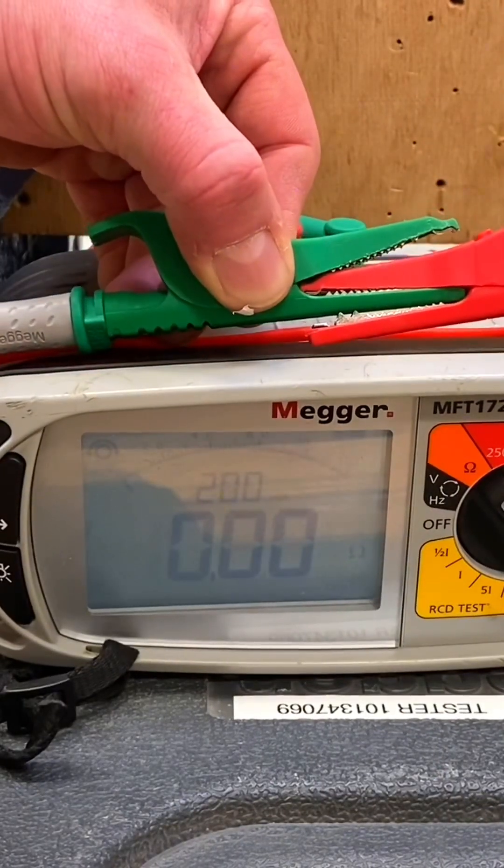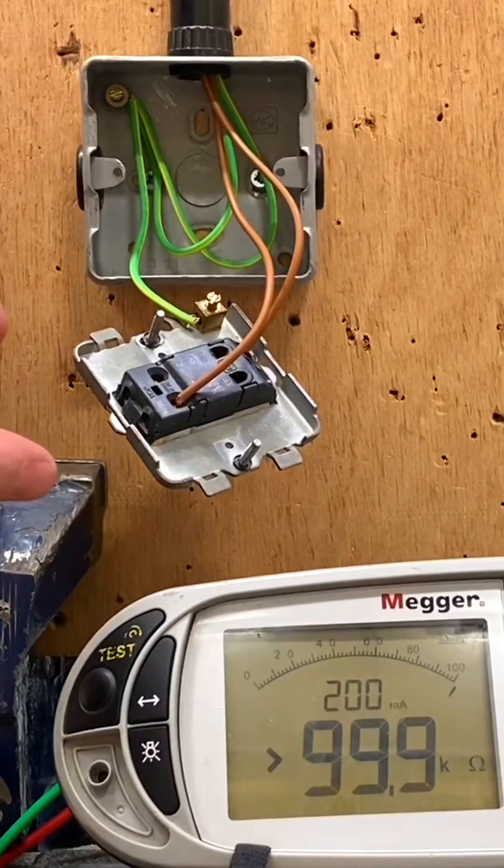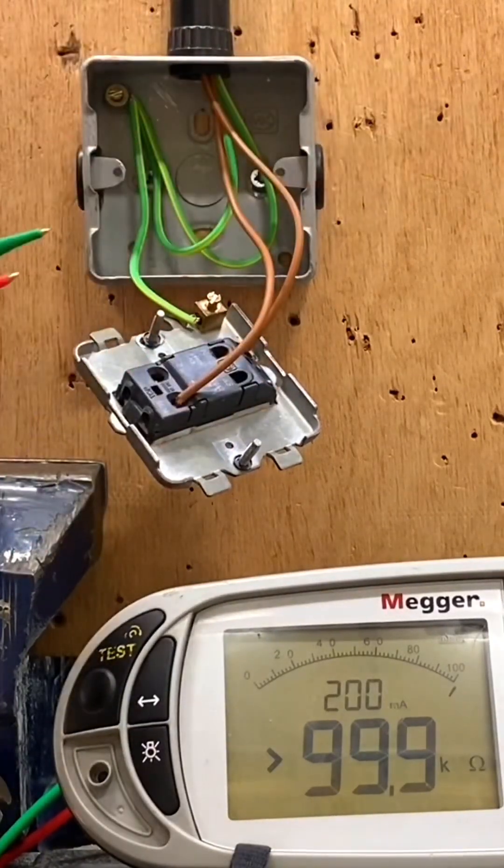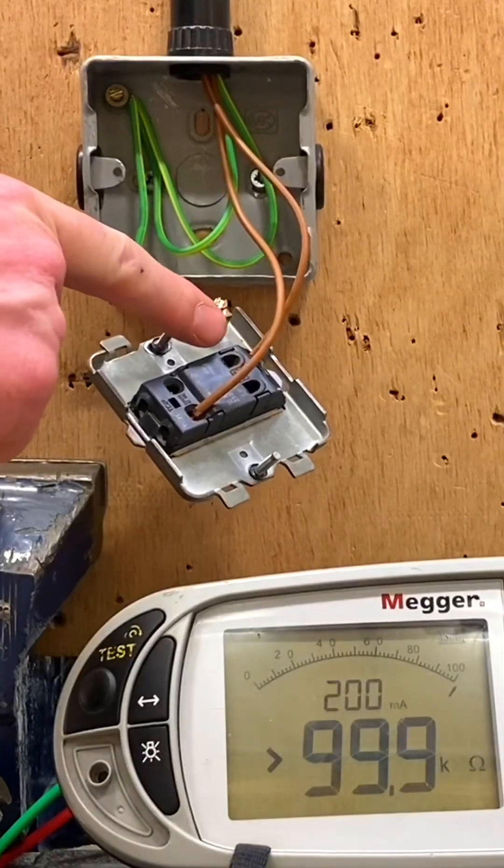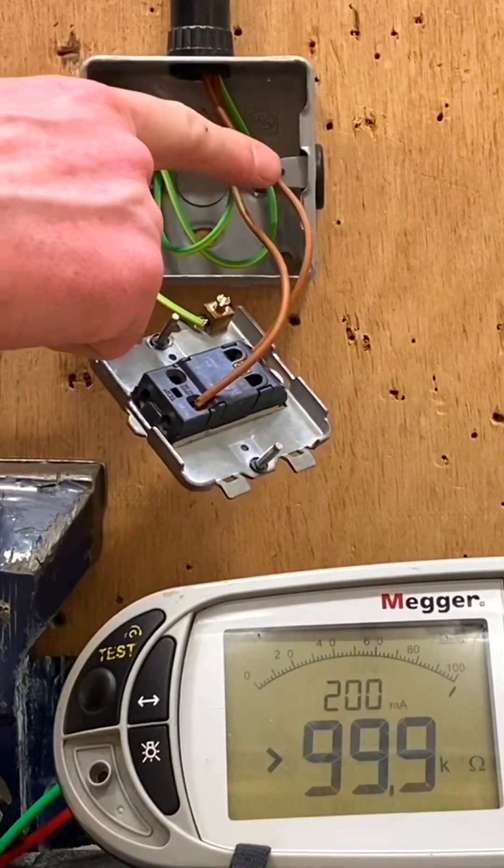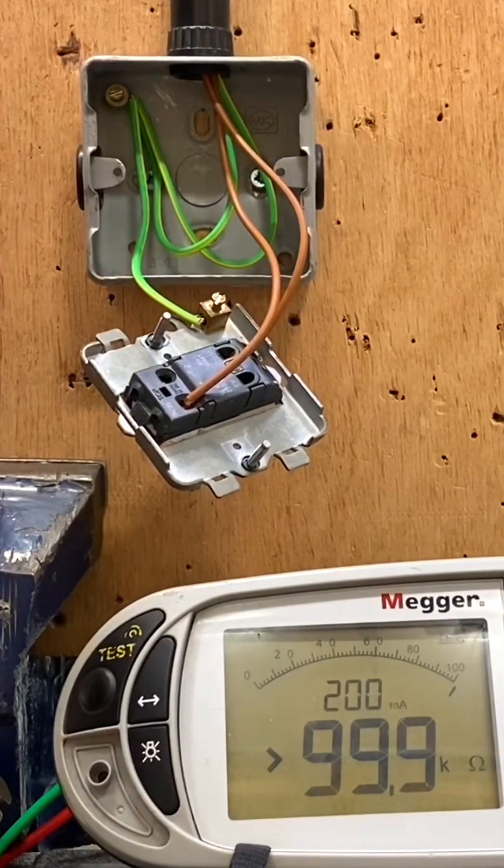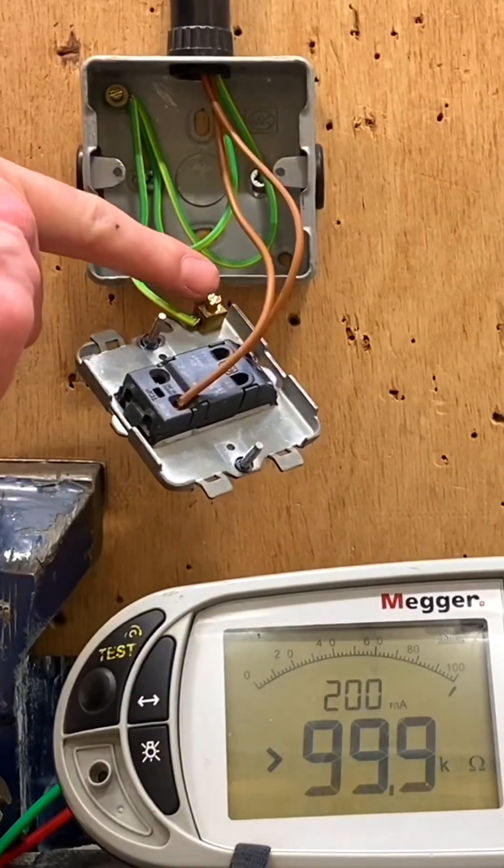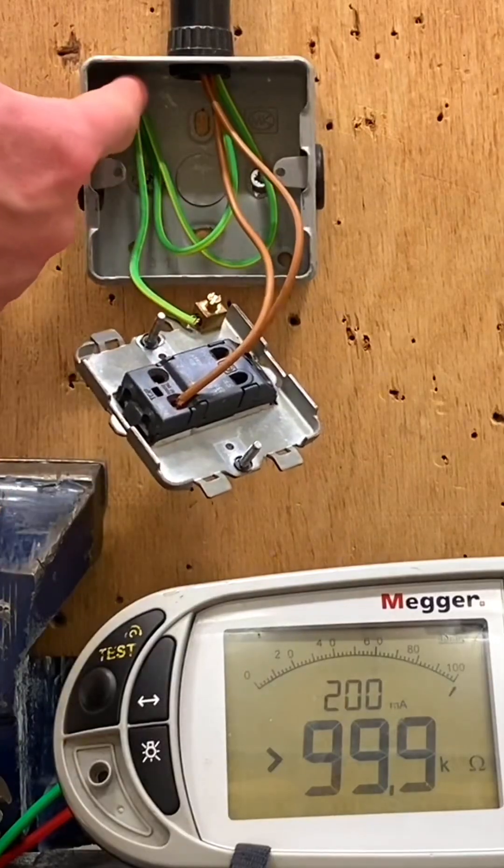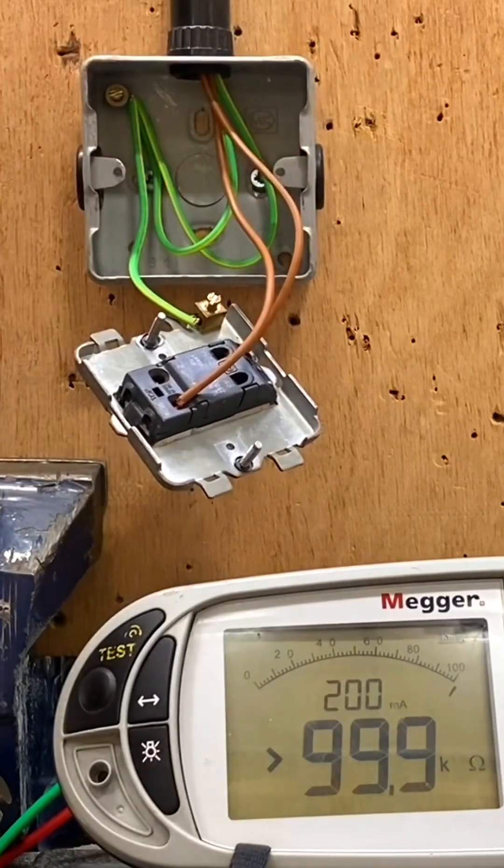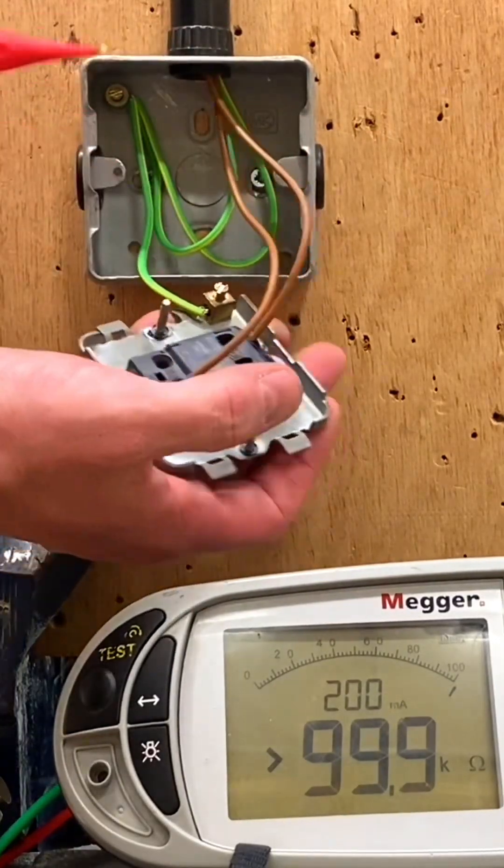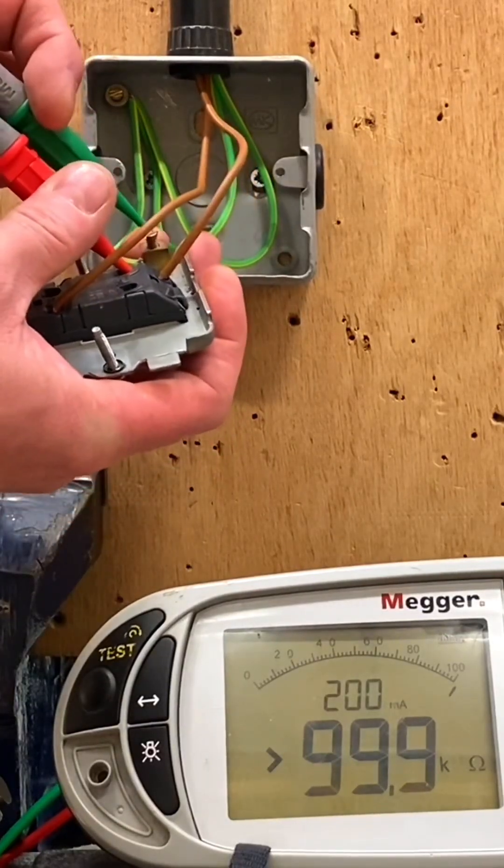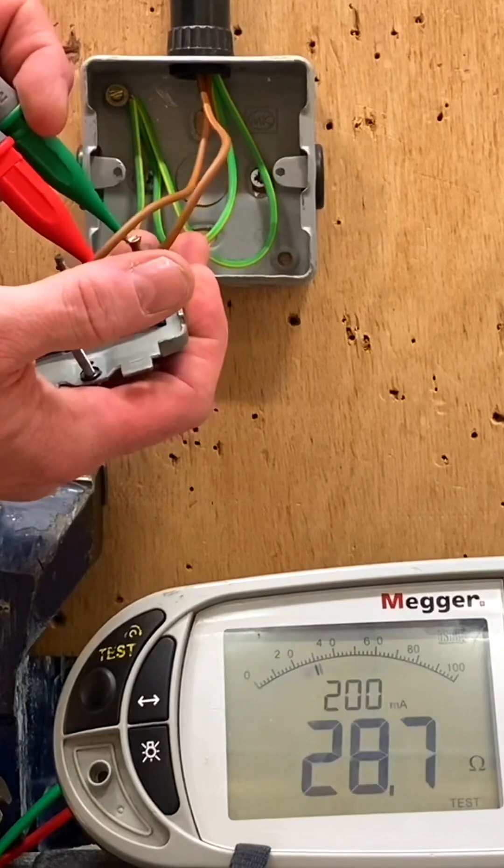I'm going to connect into the common of the switch - this brown conductor being the permanent line from the consumer unit. The other brown out of L1 is the switching line to the light. I'll connect to the earth terminal, the frame, the earth terminal, and the box to prove that all are connected to the CPC. I'm in common and onto the earth terminal at the same time, and we get 0.2 of an ohm.